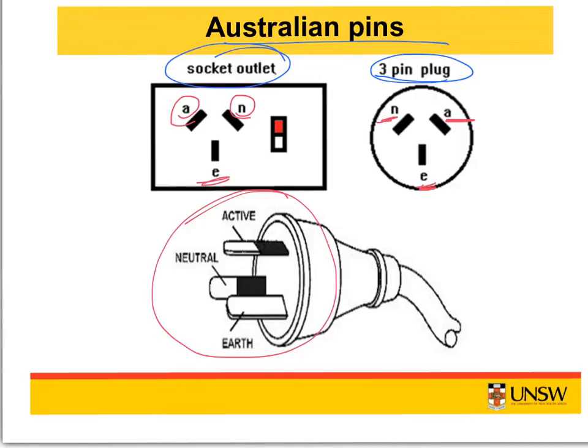Now it doesn't matter which way the pins are from an operational point of view, but it does matter for safety. Let's take a close look at what happens if we swap the active and the neutral wires in a pin. So every electrical conductor is protected by a circuit breaker. The purpose of the circuit breaker is to prevent the building wiring from overheating as a result of excessive user loads being plugged in. So the active wire normally goes through a switch at the circuit breaker and the neutral wire goes to the equipment directly.